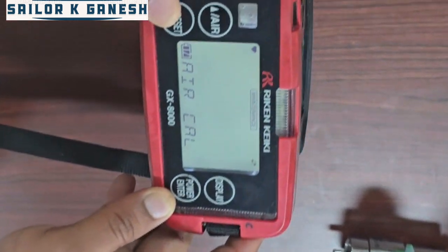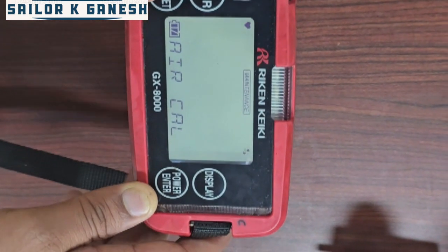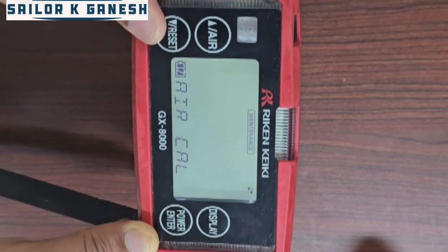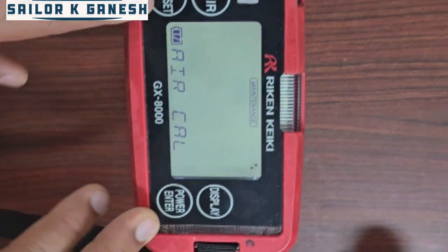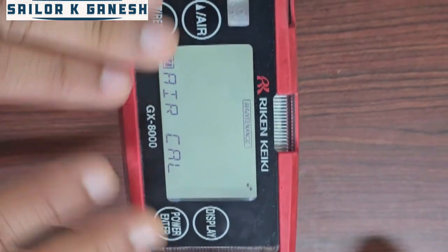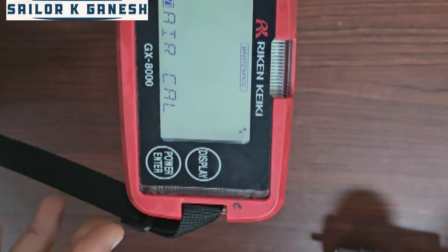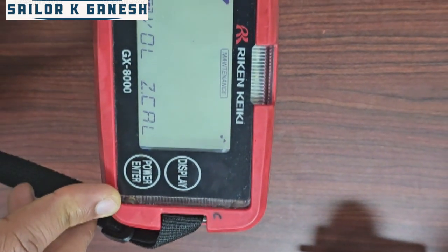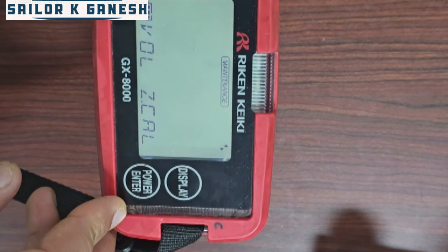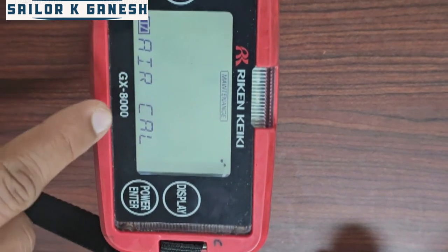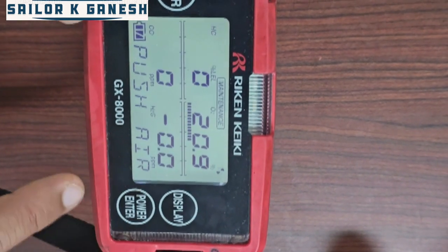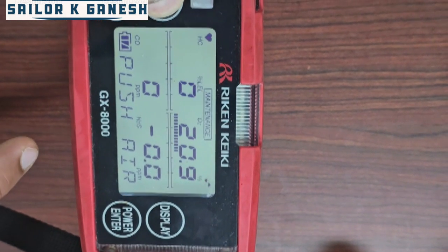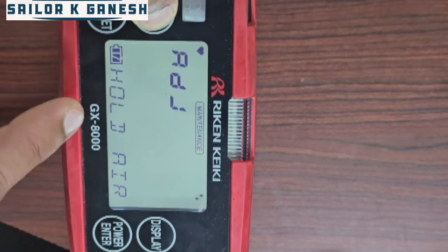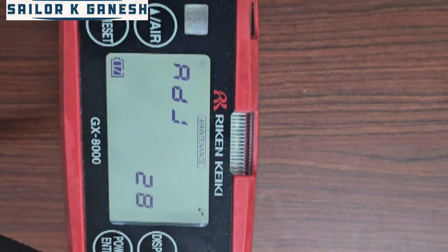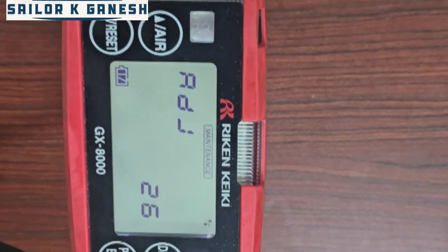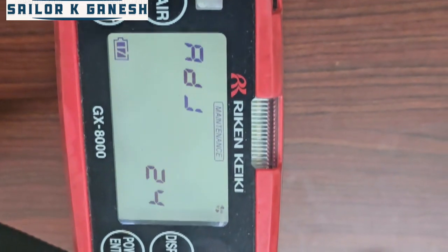Now we go for the air calibration. Okay, this is air calibration. It is required every time when you are going to check the gases in the tank or any hazardous atmosphere. So this air calibration is a normal air purge to the atmosphere. Press and hold this air key. Go back and here we have air calibration already in this mode. Press enter. Now push air from here. Hold the air, adjust and then release. Now in 28-30 seconds it will calibrate for the fresh air calibration.